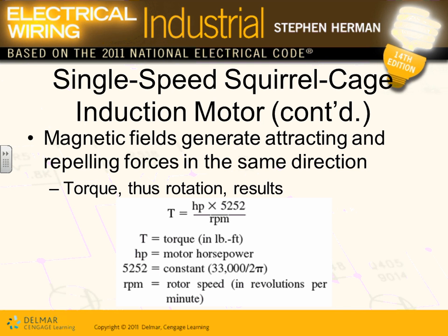A major advantage in terms of torque. If you spin it at a higher speed, the torque goes what? Lower. So there's a relationship between the torque and the speed. As the speed goes up, the torque goes down. And there's some adjustment with the VFDs for them. Any comment, guys, about this formula? T stands for the torque, the twisting force: horsepower, multiplied by the magic number 5252, divided by RPM.